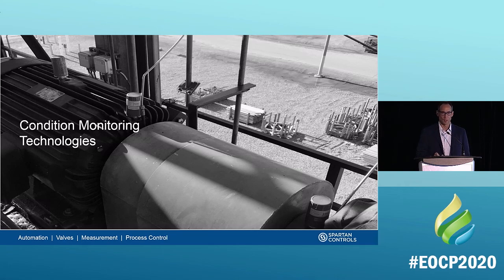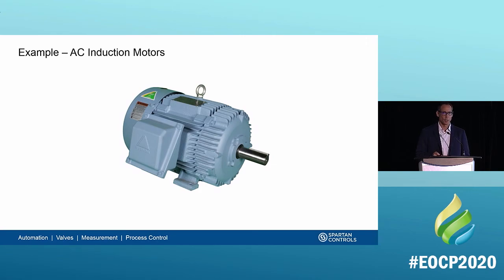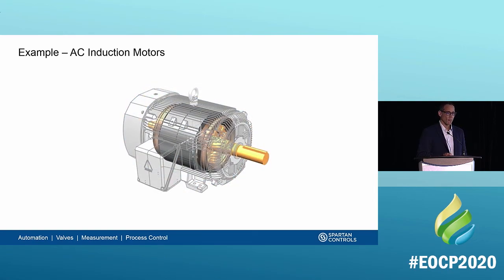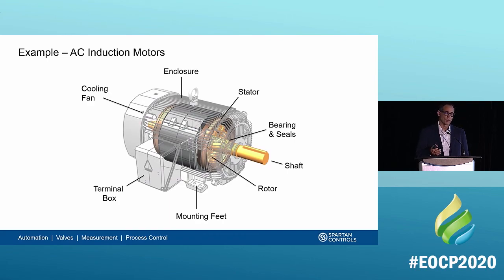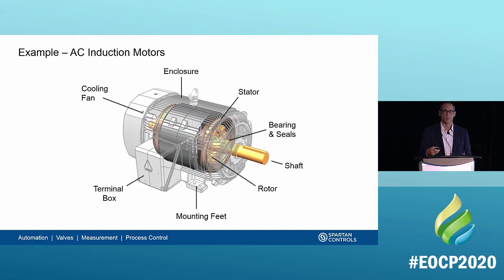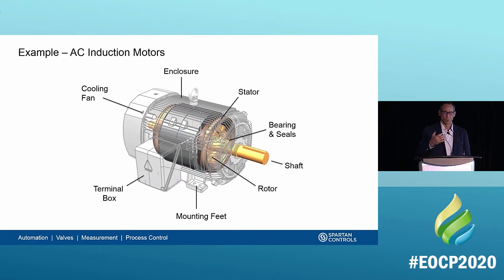Now let's talk about the specific technologies involved in condition monitoring. We'll use the ubiquitous AC induction motor because no matter what industry you're in, you'll see many of these. Looking inside the AC motor, the key parts include the rotor and stator — electrical current applied to the stator induces a magnetic flux into the rotor, causing it to spin. The mounting feet anchor the motor to the base given the significant mass and inertia involved, and an integral cooling fan pulls cold air to cool the motor as it runs.